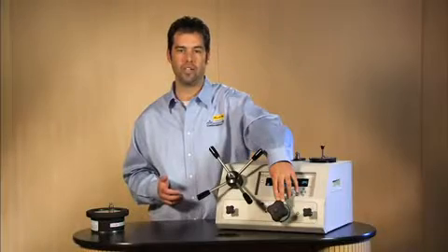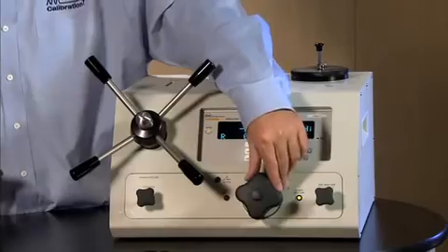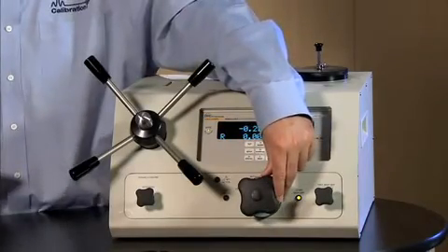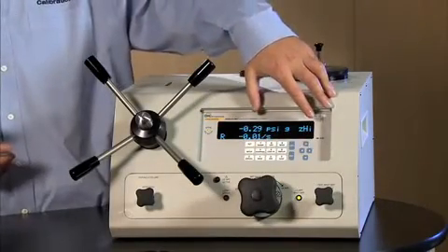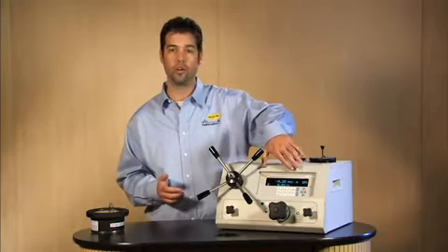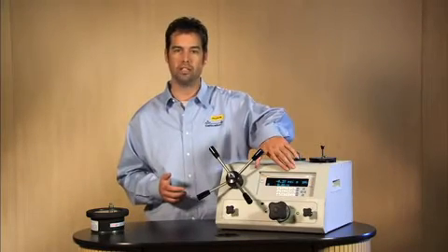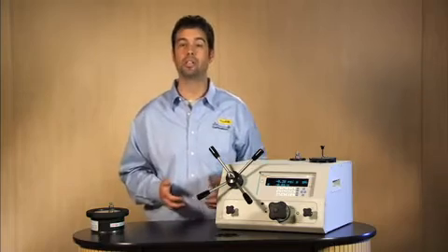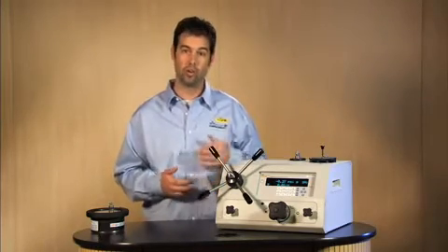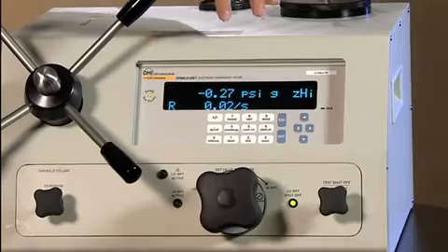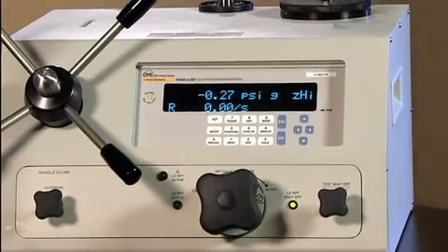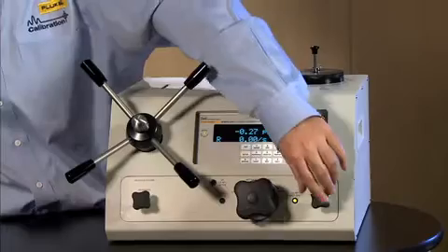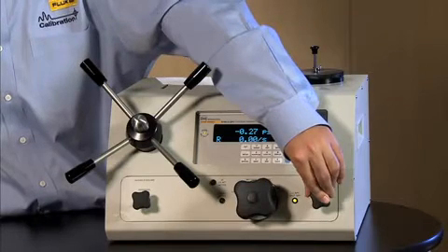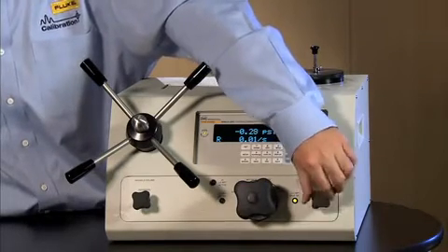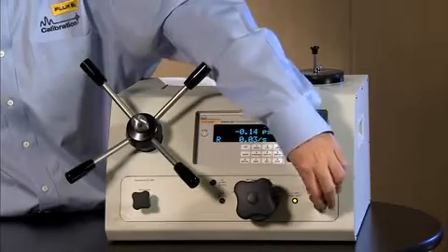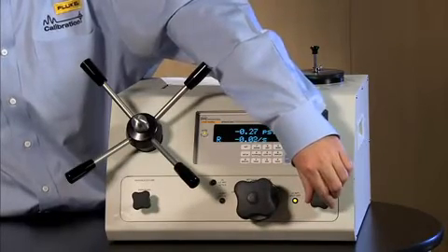The low QRPT isolation valve needs to be in the clockwise orientation to select the high transducer and isolate it from the low transducer so it is protected. We are calibrating a 10,000 psi analog gauge, which is the full scale of the high QRPT. Then we want to go to the test shutoff valve and make sure that it is fully closed. That is in the clockwise orientation.